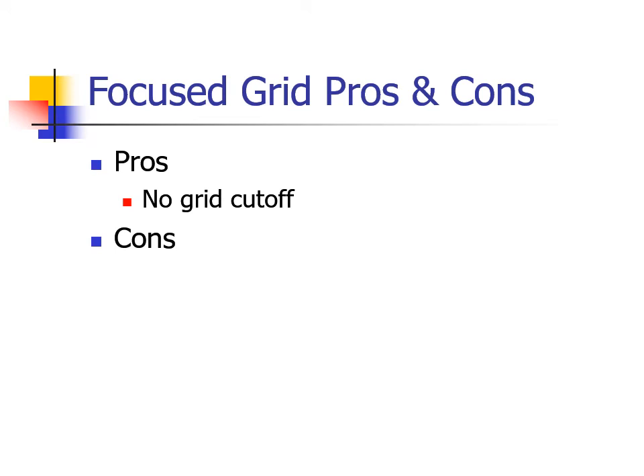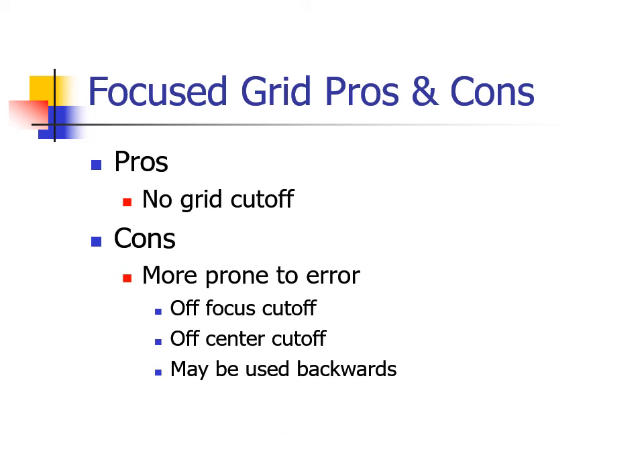On the cons side, to use this grid properly, you must position the focal spot near the grid focal length along the center line of the grid, and the grid must be positioned with its tube side up. Since parallel grids don't have these restrictions, they are better suited for portable or out-of-bucky views.